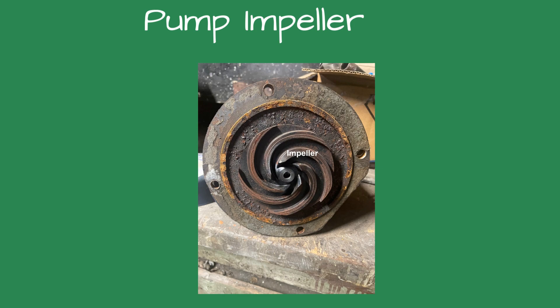As a result, the pumps ran but didn't pump anything. This caused the boiler not to have enough water and tripped the low water cutoff. Luckily, the steam did no damage to the pump impeller.